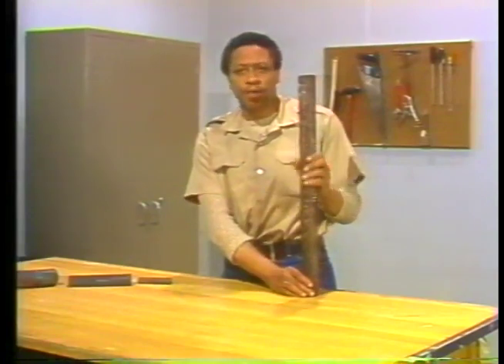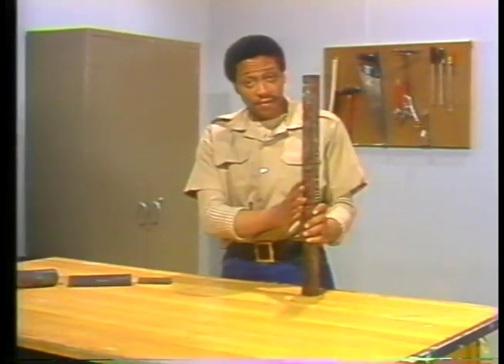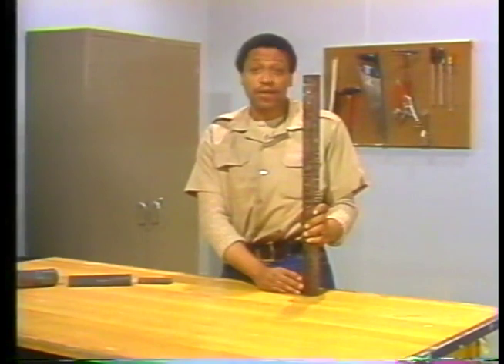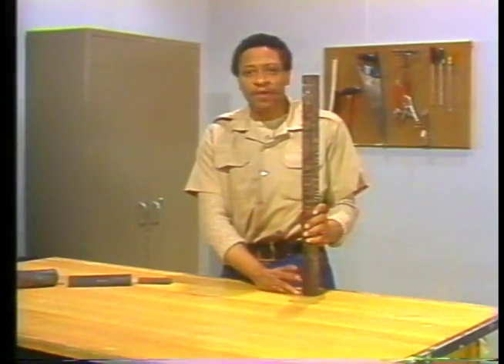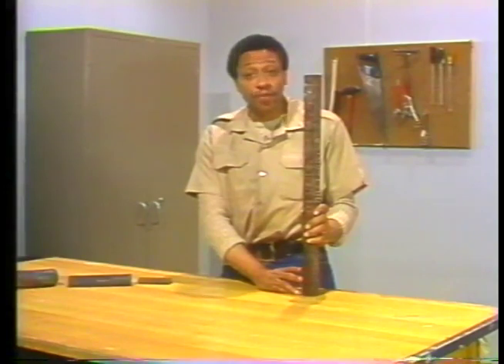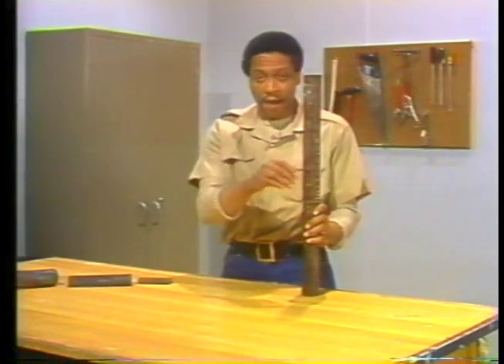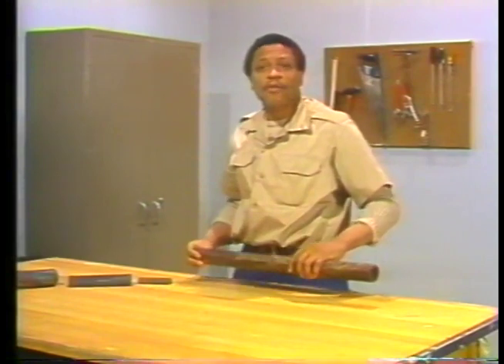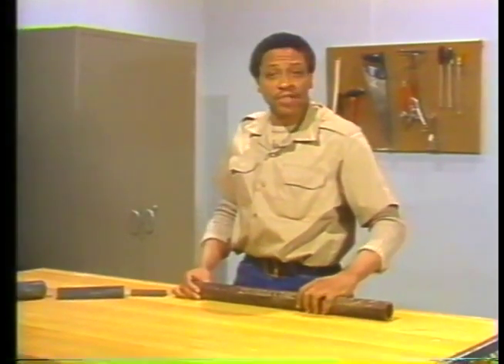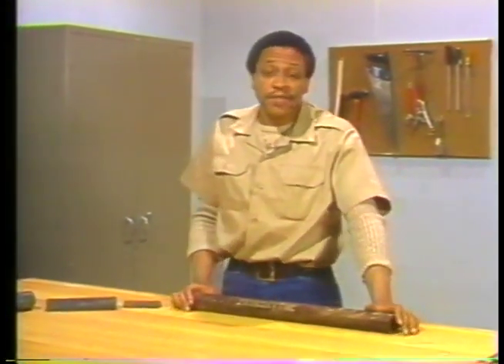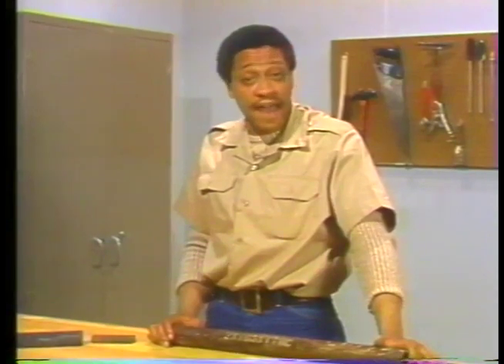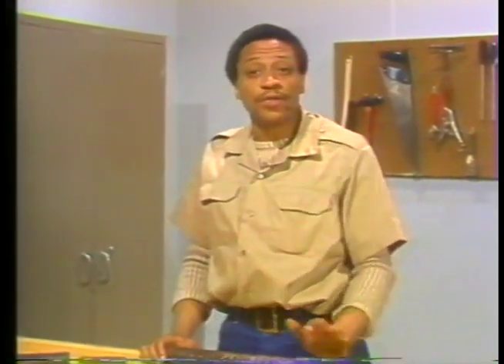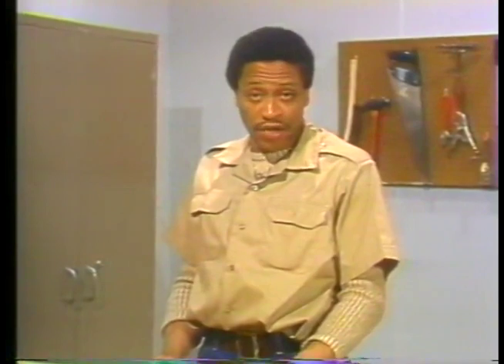The tubes used in a boiler look like the one you see here. Some are bigger and some are smaller. It looks very much like a pipe, but it isn't exactly the same. Because of boiler design requirements, tubes are almost always used in boilers. It's important to be able to tell the difference between tubes and pipes. A pipe will often have a seam that runs along its length, formed when the pipe is manufactured. Tubes, on the other hand, are manufactured so they do not have seams. Boiler tubes also usually have thicker walls than ordinary pipe.